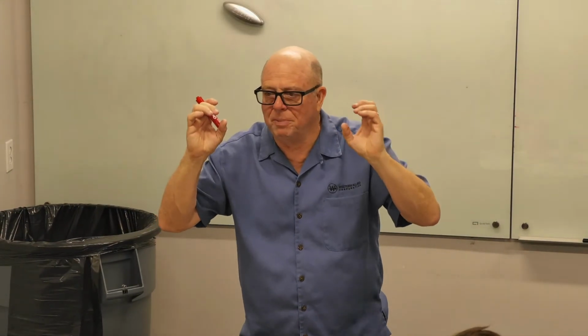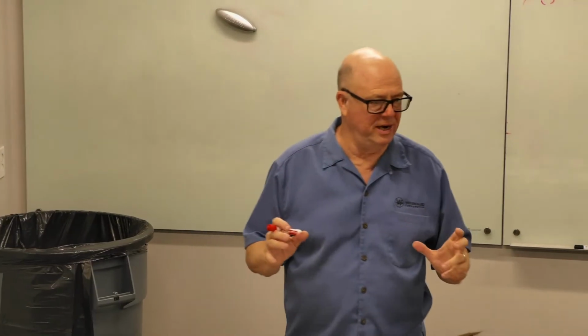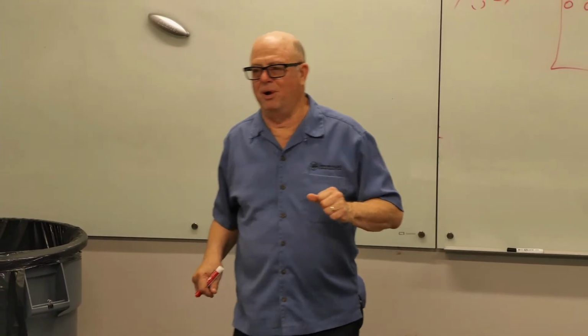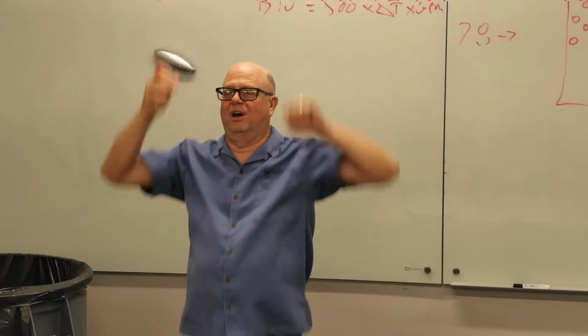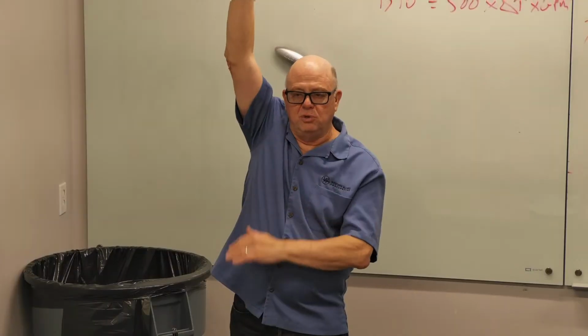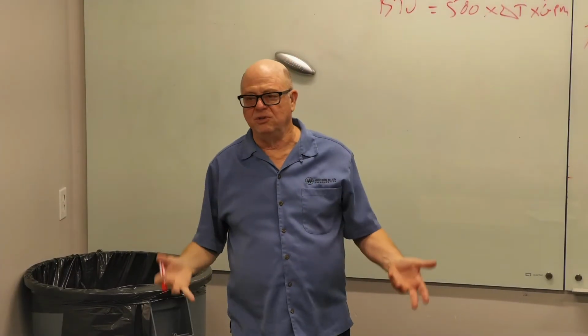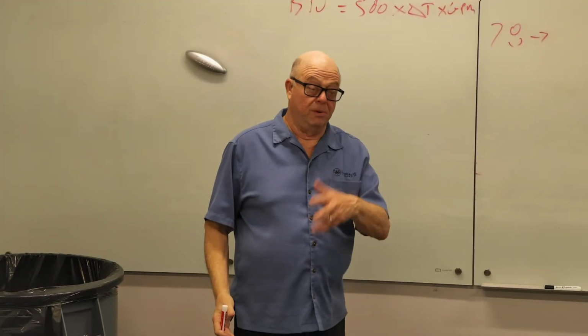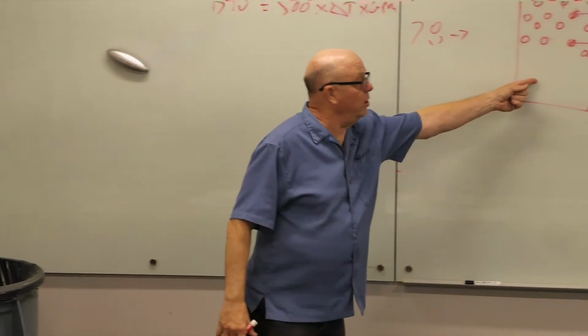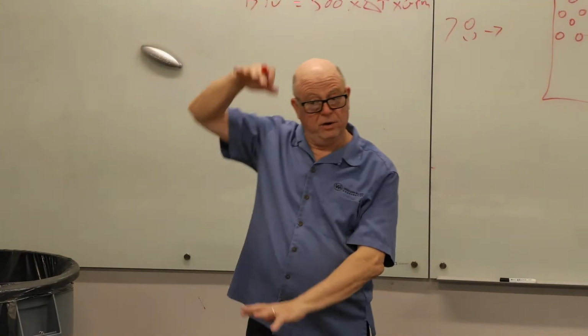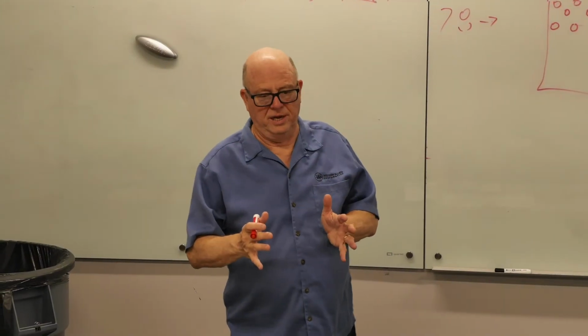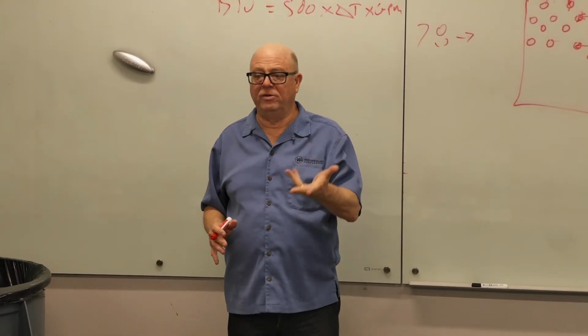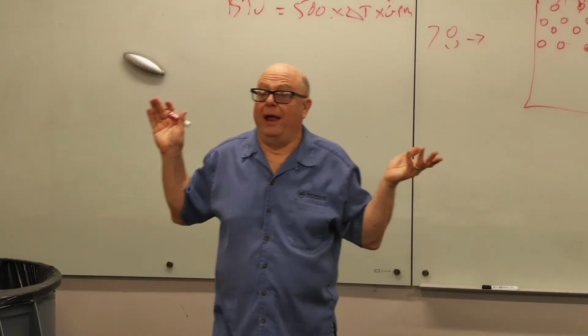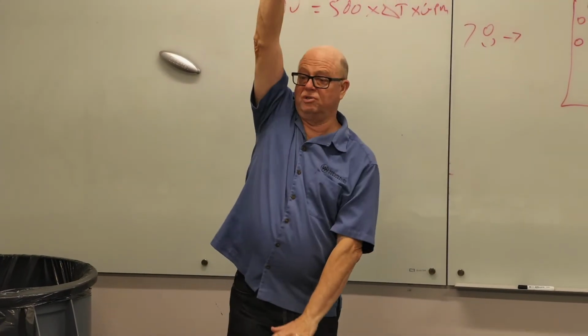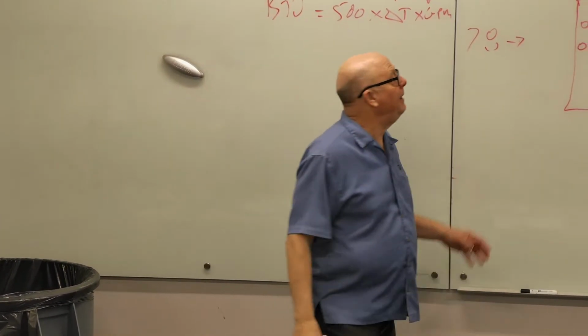Think about what that does to your pipe size, your pump size, the amount of insulation you've got to put on the pipes, the weight of the stuff, the labor. The higher the rise you use, the less expensive it is. Your limitation is probably how big of a coil you put in, because the higher the rise, usually the more coil you need. That's the trade-off. And can my chiller do that? You'll get to a rise that's so high the chiller can't do it anymore.